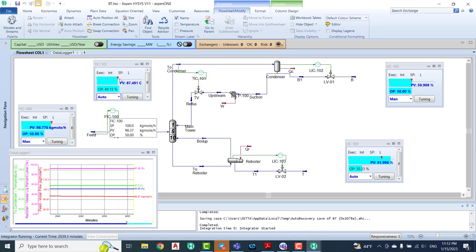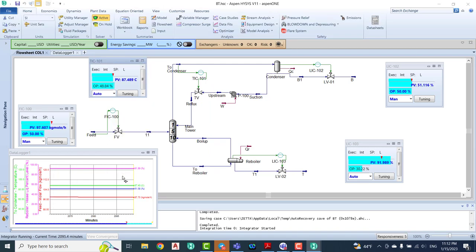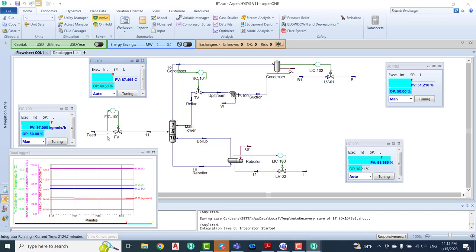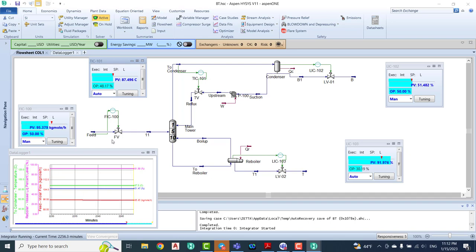All about the feed flow rate should remain in manual all the time. Why? Because in the feed we have two phases. Normally the controller and control valve can only control one phase, not more.